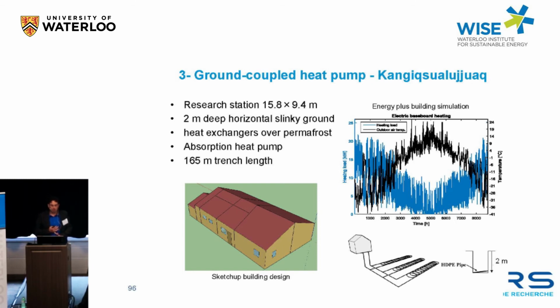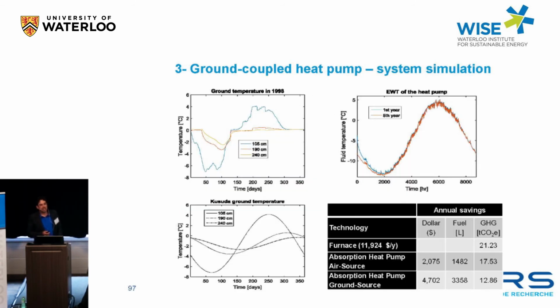Based on the subsurface properties, we evaluated a trench length of 165 meters for this house, simulating the energy loads that are shown in blue on my graph, according to the outside air temperature, the black line that goes all the way to minus 40 during the winter. So pretty tough climate. And then simulating the ground heat exchangers' operation based on historic data of ground temperature that you see in the upper left corner.